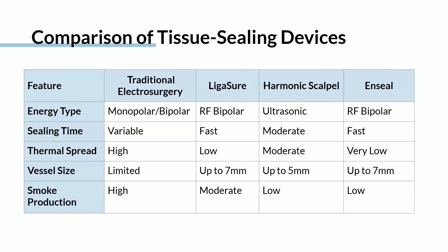For the energy device selection in surgery, this depends on tissue type and surgical approach and key considerations such as safety and cost effectiveness. For example, for fatty tissue, the ultrasonic devices like the harmonic are ideal because they minimize the thermal spread. In contrast, for vascular tissue, it's better to use the bipolar devices such as LigaSure, as we mentioned, because these provide more precise vessel sealing. For the surgical side, in laparoscopic or robotic surgery, for example, energy devices can allow more precise sealing in tight spaces where sometimes the maneuverability is limited.